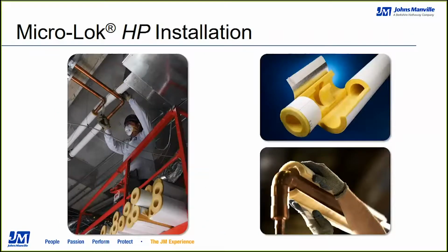The full Micro-Lok product line is produced on mandrels, rolling the insulation in layers to achieve the desired finished thickness. This offers installers the ability to fillet out small portions of the fiberglass to cover low-profile fittings. The products also come imprinted with the pipe diameter and wall thickness, as well as the size for corresponding PVC fittings on the jacketed material.